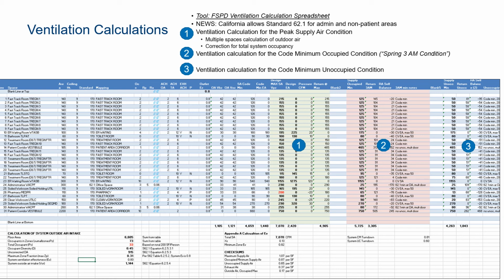The first step is that you're going to have to do a system maximum air calculation. That should be at the block peak, not the sum of space peaks, or at least I'm told. So this one is for a 7,000 CFM air handler. The sum of the zones might be 8,000 CFM, but you should be doing your ventilation calculation, your outdoor air calculation, at the maximum simultaneous peak. The second calculation that you need to do is at the minimum occupied position.